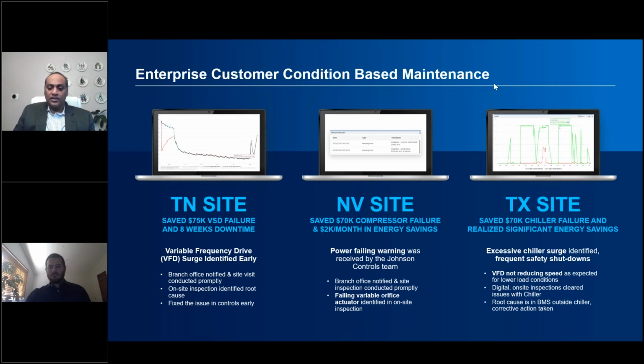The third example, you can see the data. It's a little small, but it's there. You can see those green bars go up and down very dramatically. That's not how a good chiller should operate; it should be a nice smooth line. So the data pattern again indicated there was a problem.